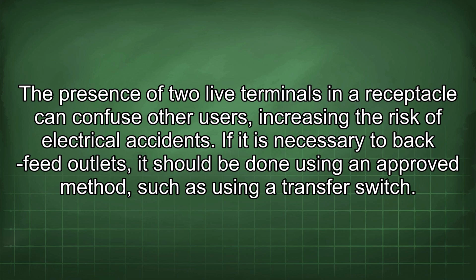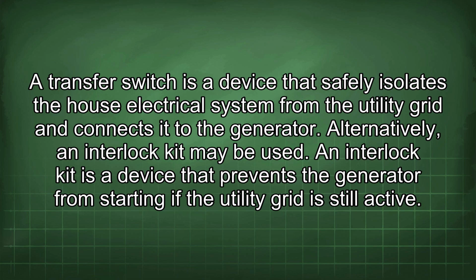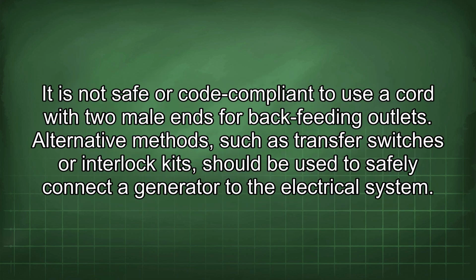If it is necessary to backfeed outlets, it should be done using an approved method, such as using a transfer switch. A transfer switch is a device that safely isolates the house electrical system from the utility grid and connects it to the generator. Alternatively, an interlock kit may be used. An interlock kit is a device that prevents the generator from starting if the utility grid is still active. It is not safe or code compliant to use a cord with two male ends for backfeeding outlets. Alternative methods, such as transfer switches or interlock kits, should be used to safely connect a generator to the electrical system.